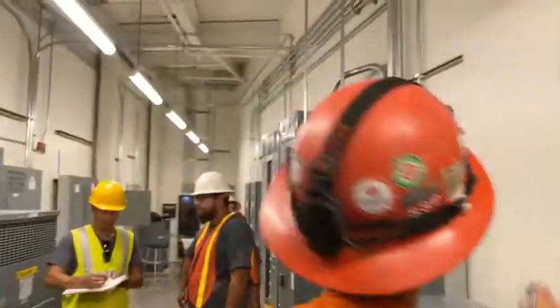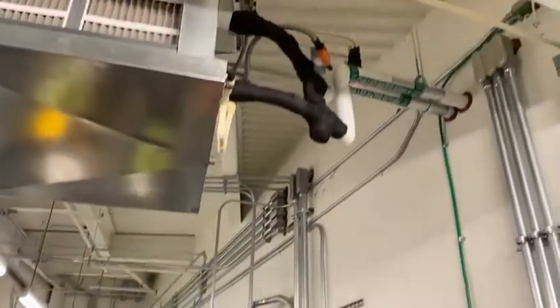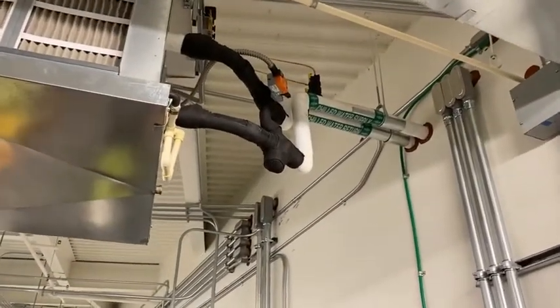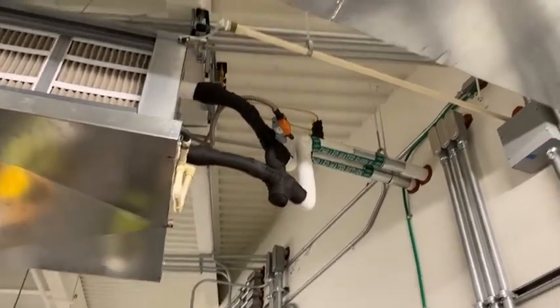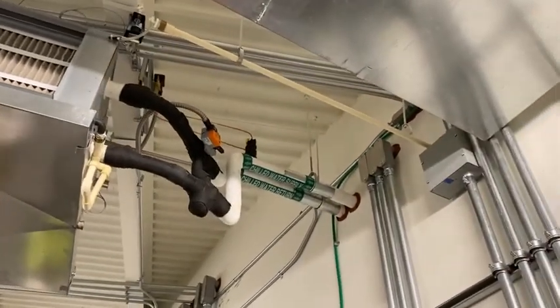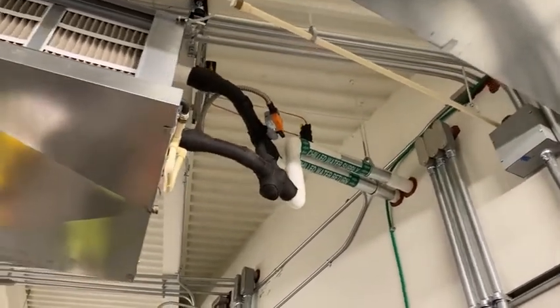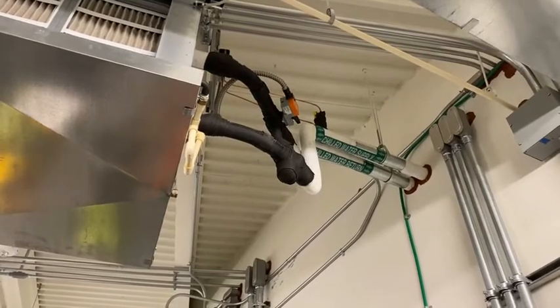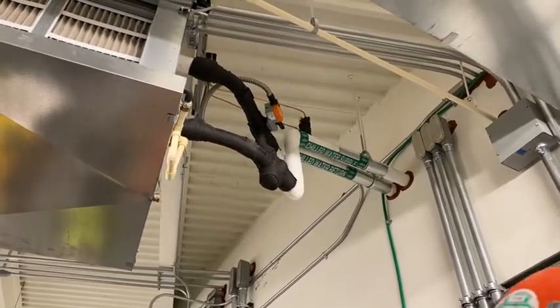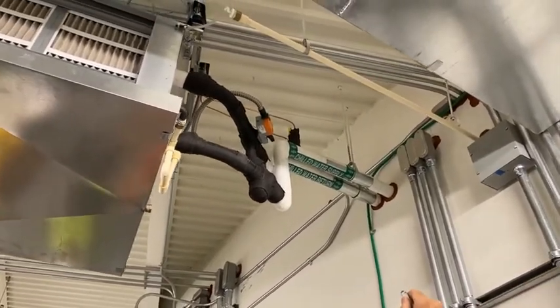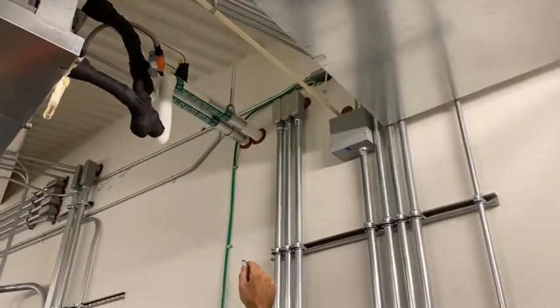Chilled water only going into this fan coil. You've got supply and return here. We have a strainer down here, control valve up here. The valve is open. The pointer is in line with the pipe right now. If you do have to take the actuator off, make sure you pay attention to the valve itself. You can install these backwards to where that would be closed, and if it was facing down, it would be open.